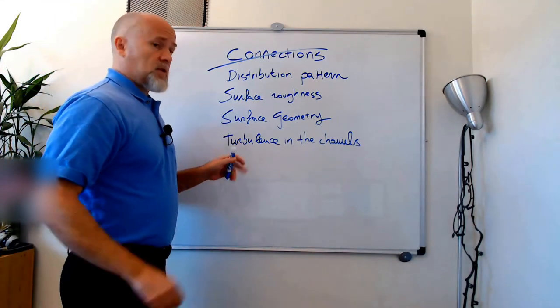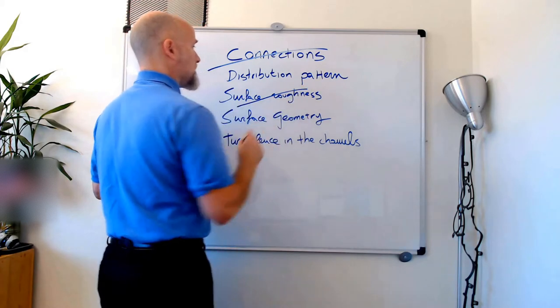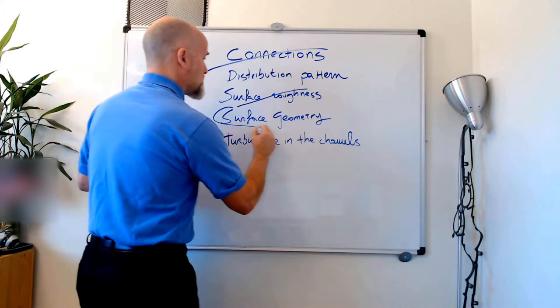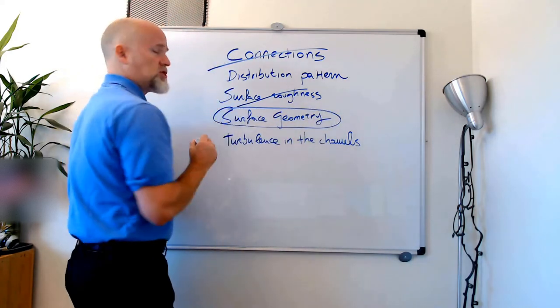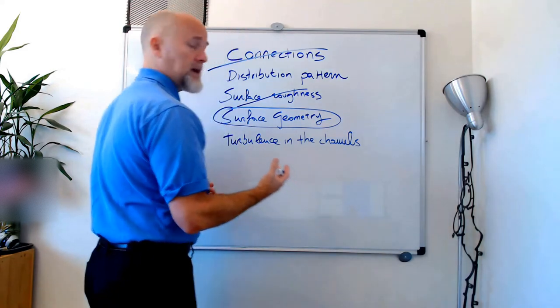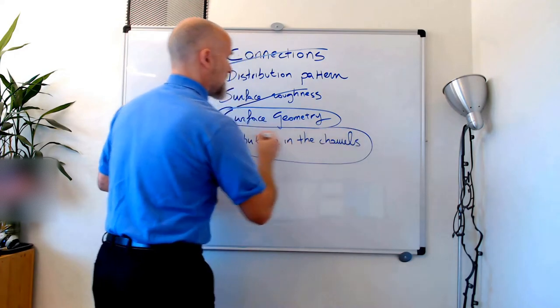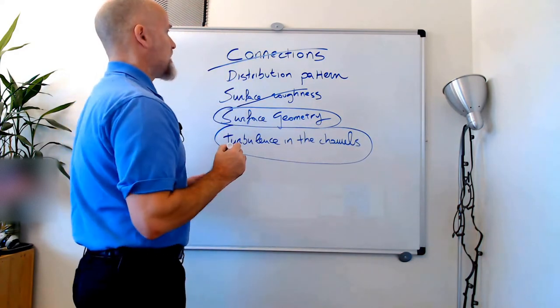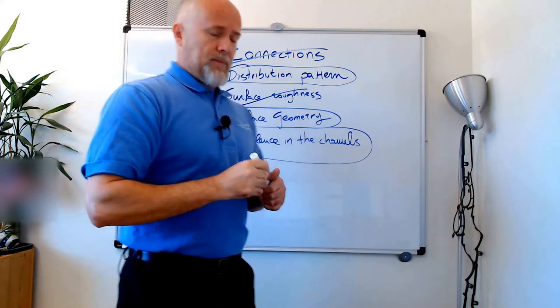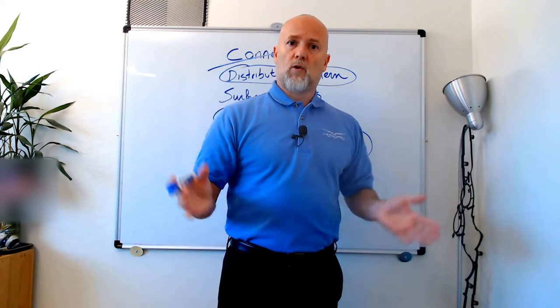You don't want loss of pressure drop because of the roughness of the plates, but you want pressure drop based on the geometry, assuming it's a modern geometry that facilitates the shear stress. You definitely want turbulence in the channels and equally you want a modern distribution pattern that covers the whole plate with the fluid.